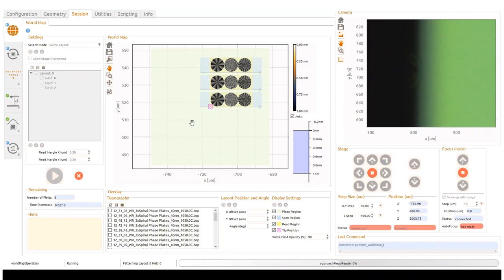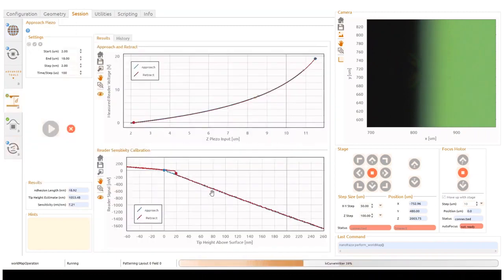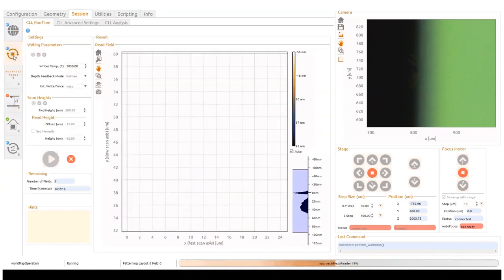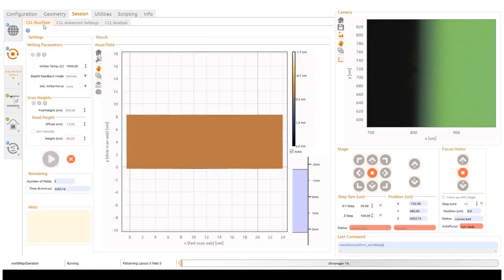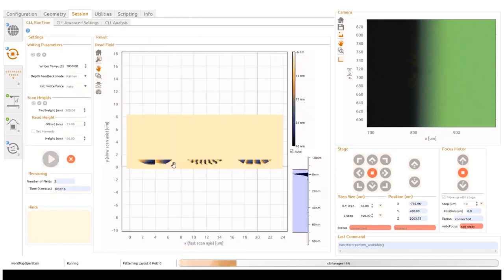And then we go to our session window and press the green button, and off it goes, starting the patterning of these three fields. First, it's doing again, of course, some calibrations. It takes some time, so it's doing an approach, finding the surface again, and calibrating the scanners. You can check the default parameters here for the temperature and so on. There are a lot of advanced settings, but usually you don't need to worry about them. You just need the CLL runtime window here.